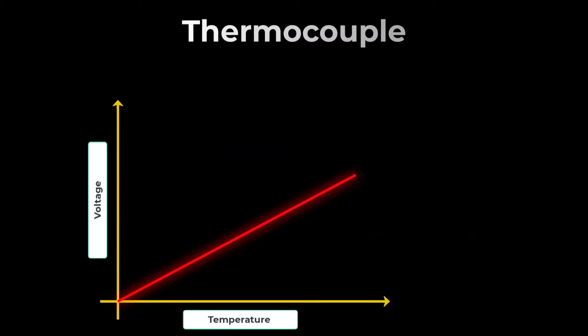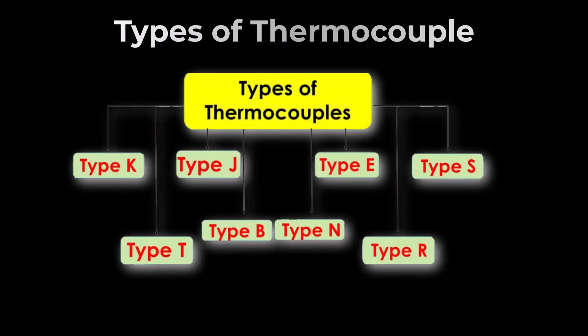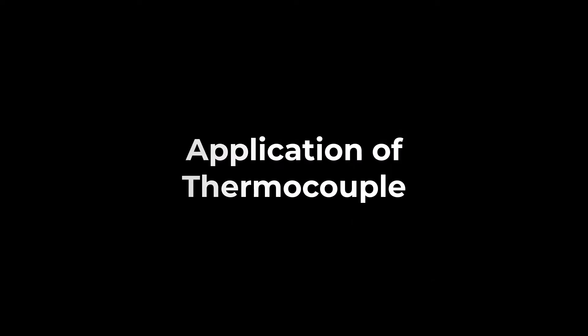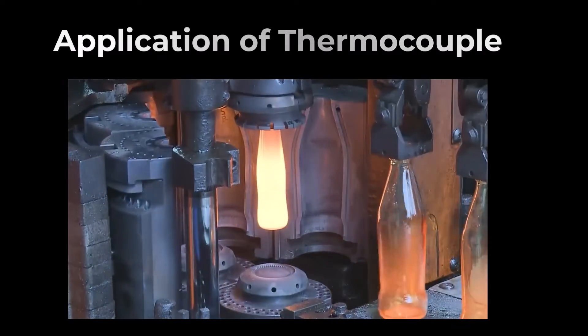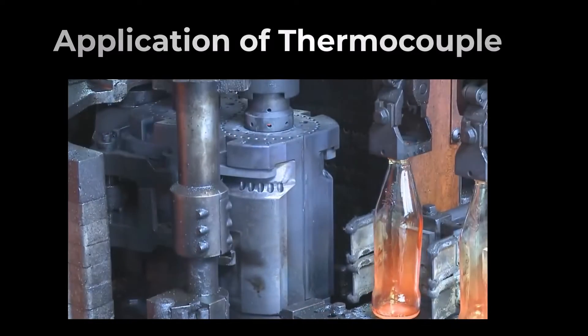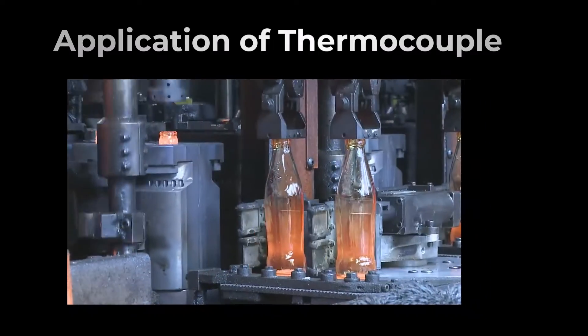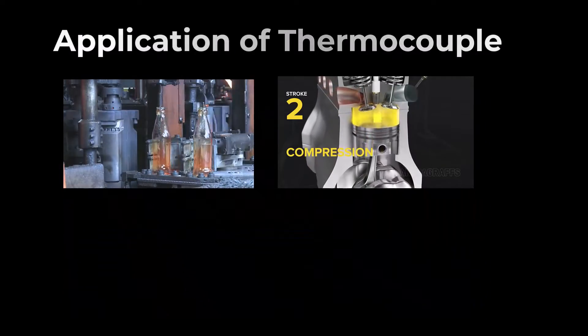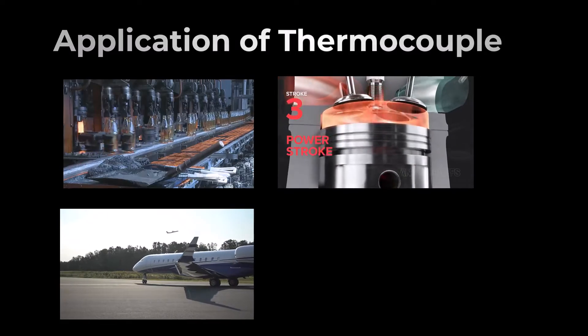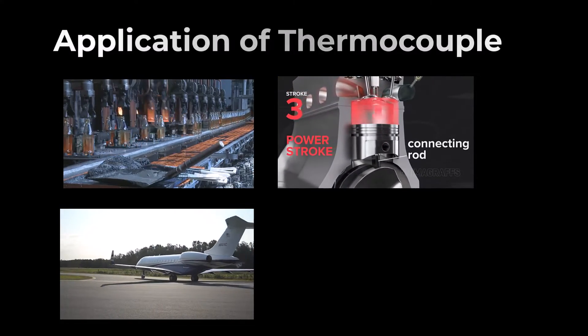The generated voltage, also known as the Seebeck voltage, is measured across the open ends of the thermocouple. By calibrating the relationship between voltage and temperature, the thermocouple provides an accurate temperature reading. Common types include Type J, Type K, and Type T, using combinations of metals like iron, constantan, nickel, and copper. Applications include industrial process monitoring, automotive exhaust gas measurement, aerospace temperature measurement, and HVAC systems.